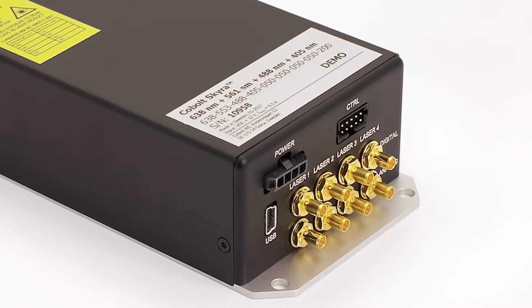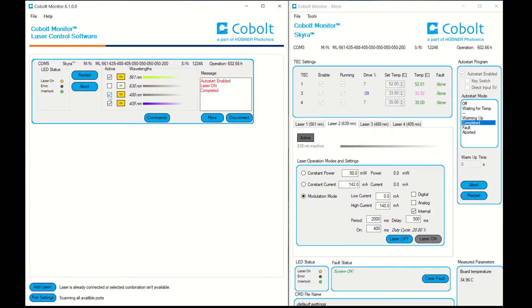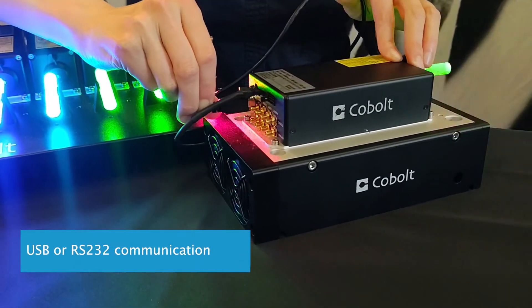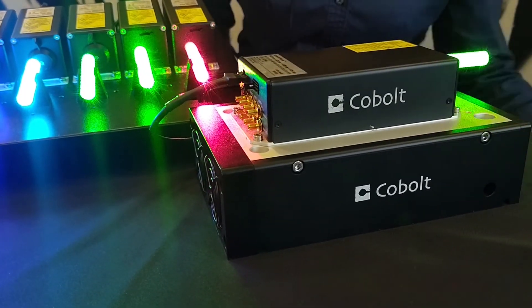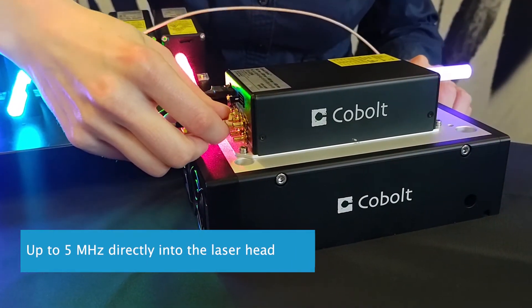Another important aspect of the system design is the ability to control and communicate with the laser via software. The user-friendly control and integrated electronics of the Cobolt Skyra allow for several control options via software and custom automation programs, which make it easy to integrate the laser into a light sheet microscope. Programming the laser wavelengths for on-off operation greatly reduces the equipment needed to integrate and operate the laser. Modulation signals can be sent directly via USB or RS-232 communication through software written with Python, C++, LabVIEW, Micromanager, or Cobolt's GUI. And megahertz modulation speeds are also possible through direct 5V signals on the laser head.